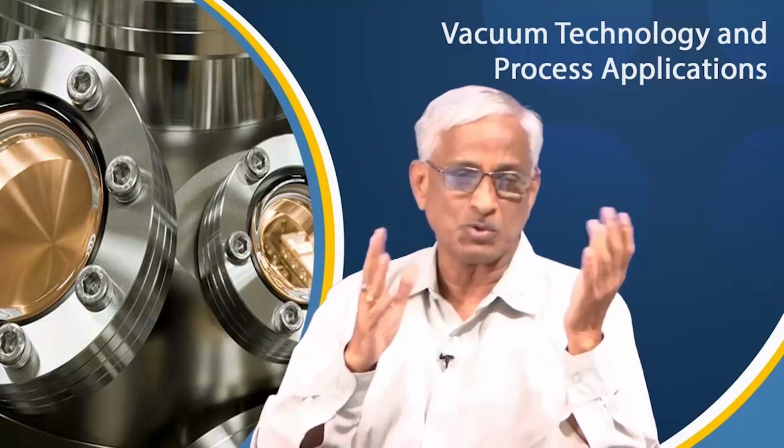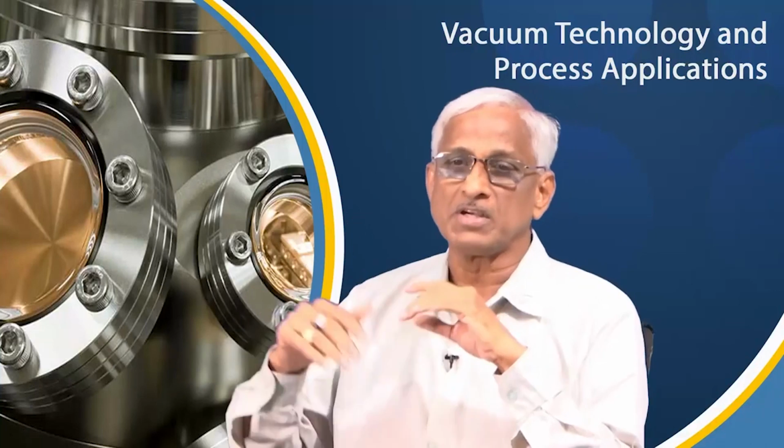There are two types of manufacturers in vacuum pumps, up to 10 power minus 3 rotary, roots blower, etc. And minus 3 onwards diffusion, turbo, ion, cryo, they will be different level of vacuum. So, technologies are equally challenging in both the places.